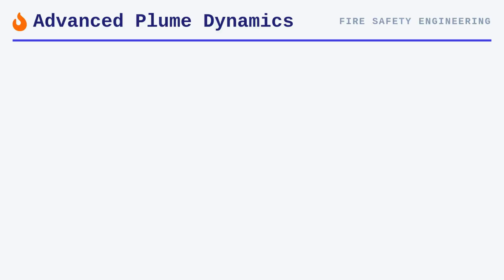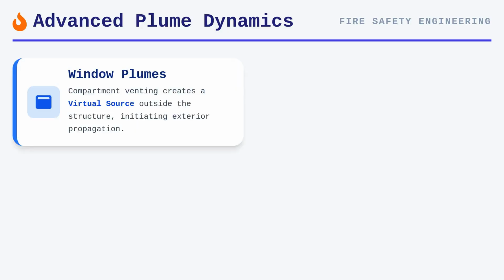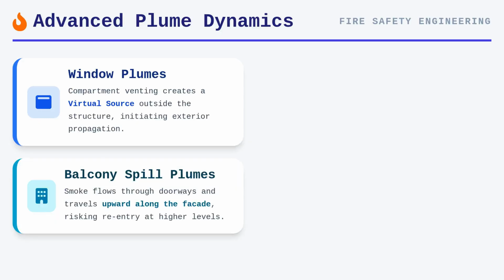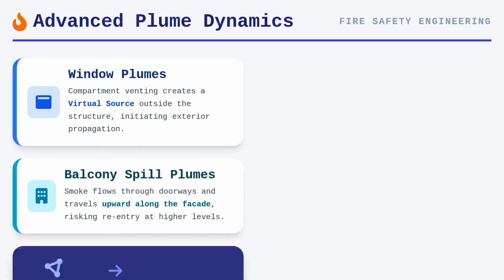The complexity increases significantly when we introduce specialized plume configurations, such as balcony spill plumes or window plumes resulting from compartment venting. A window plume occurs when a fire inside a room vents through an opening, effectively creating a new virtual source for the smoke outside the structure. Similarly, balcony spill plumes occur when smoke flows out of a doorway and travels upward along the exterior facade, potentially re-entering the building at higher levels. These scenarios demand an understanding of virtual origin concepts, allowing us to treat non-point sources as equivalent point sources to simplify the math.